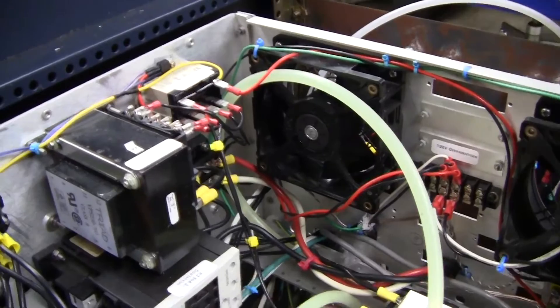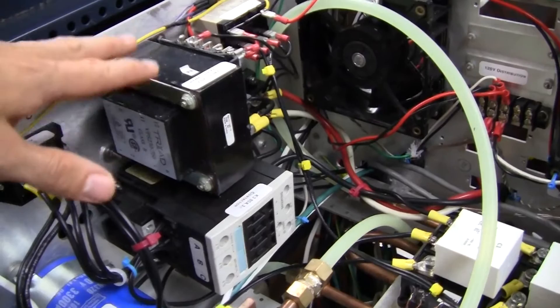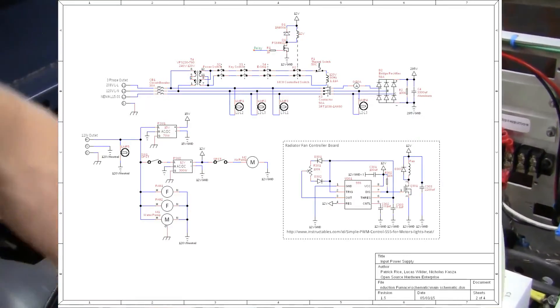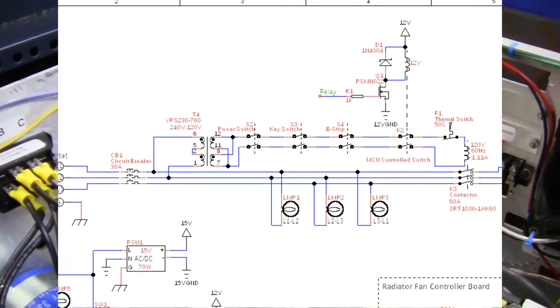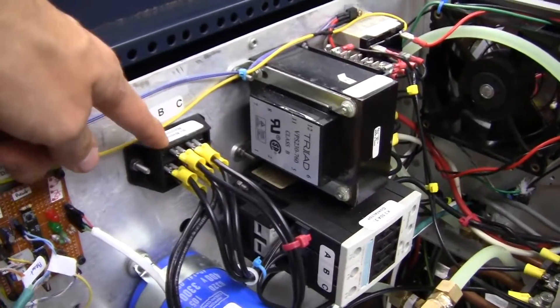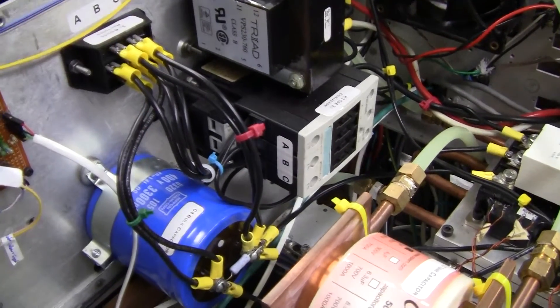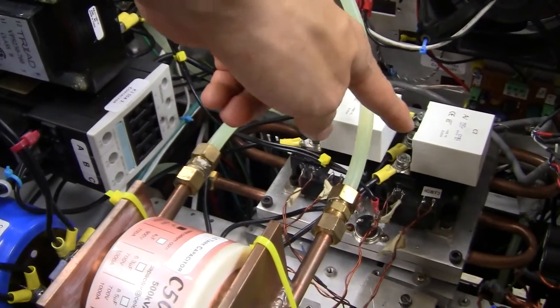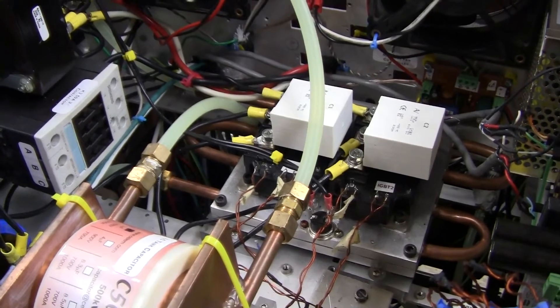On this other side we have the three-phase input. Here's the contactor, and up here is the 120-volt circuit that engages this contactor, which engages the relay to close the contacts. After the contactor there's a three-phase bridge rectifier, and then it goes into the bulk capacitor down there. This DC then gets switched into high-frequency AC with those IGBTs.